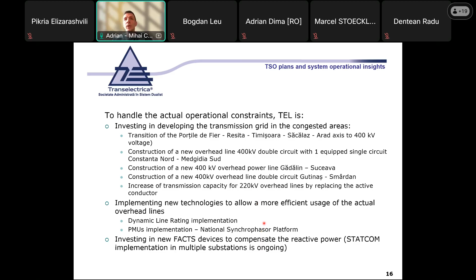To cope with transit flows, we also plan to install dynamic line rating, and we have a great PMU implementation, the so-called National Synchrophasor platform. For voltage regulation, we will be investing in new FACTS devices to compensate reactive power, and the technology picked is STATCOM. The implementation is ongoing.